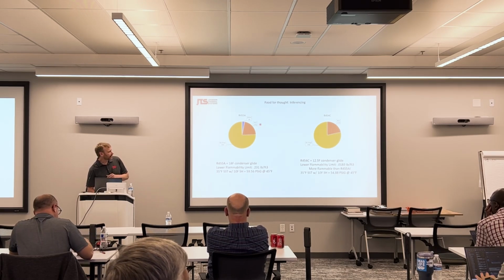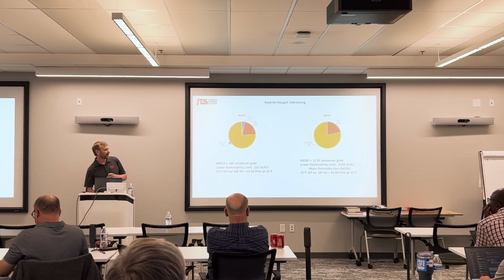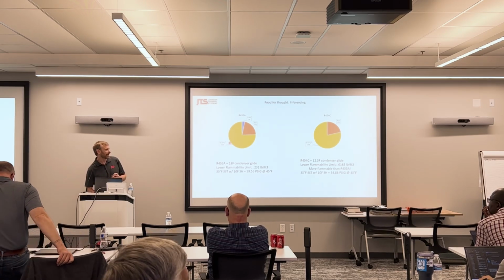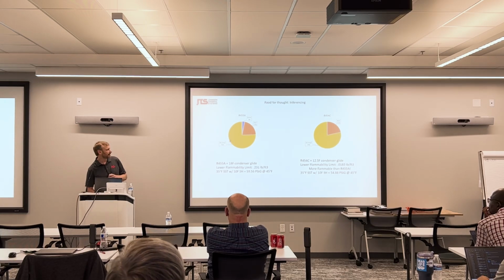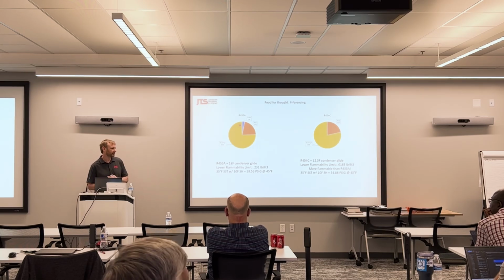So R32 and R1234YF are both A2L refrigerants. They're both mildly flammable. But they've added this CO2 component to make it less flammable. Gotcha. And the consequences are, by adding it, it's increased the amount of glide of the refrigerant, but it's made the refrigerant substantially less flammable. Yep, I see now, it's the CO2 that is going. Right.